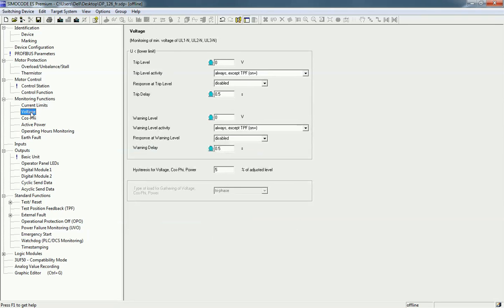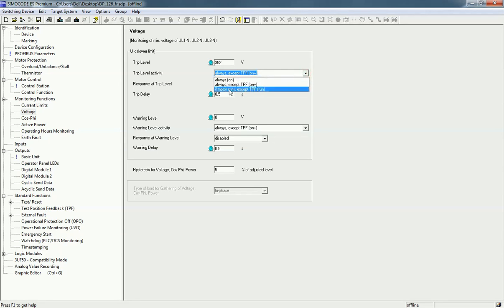For voltage monitoring, you can select lower limits and there are also options for warning and trip levels. I will set it so that when voltage crosses 350 V with activity always on, the response at trip level is tripping, and the delay is set to one second as per the application.